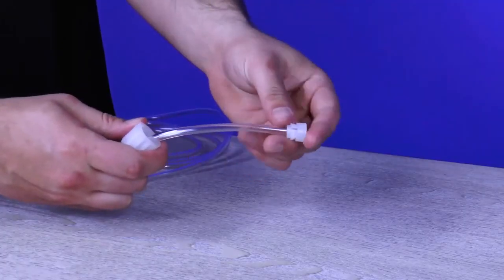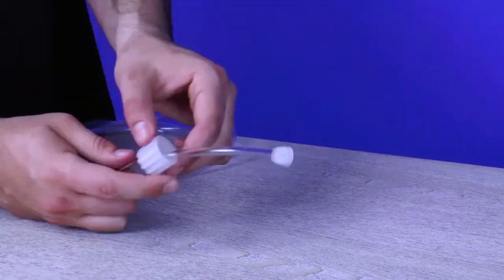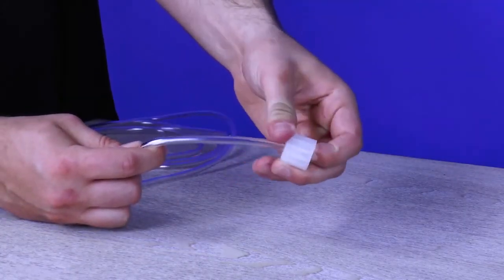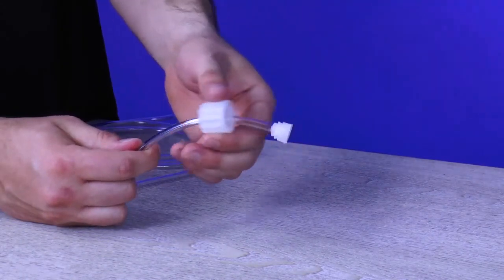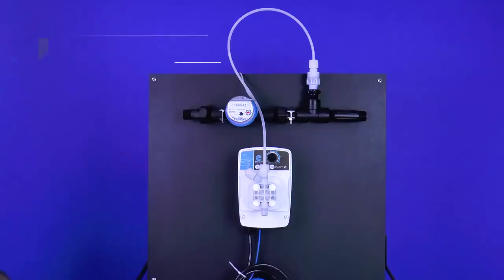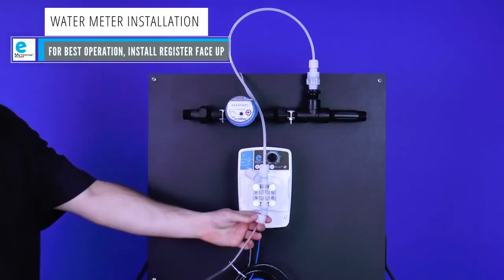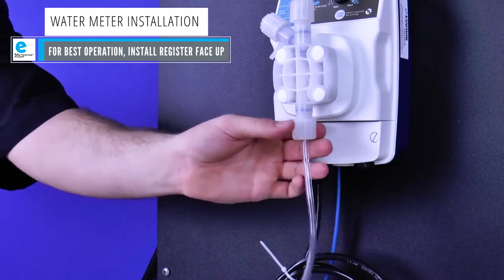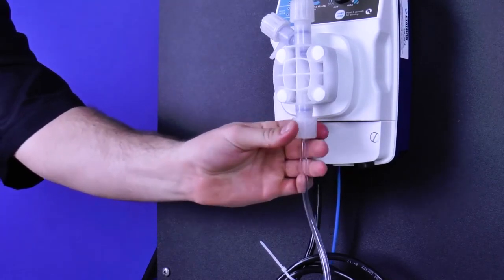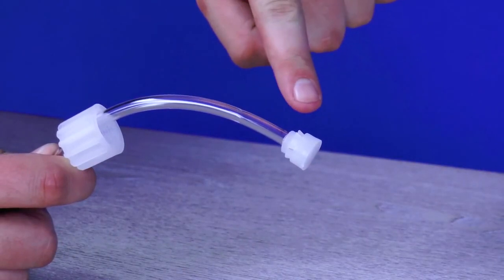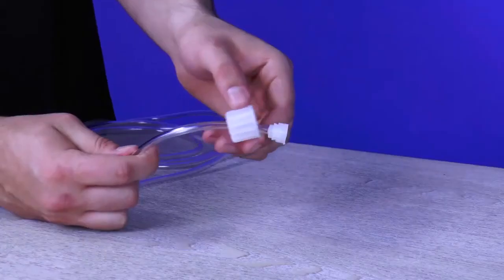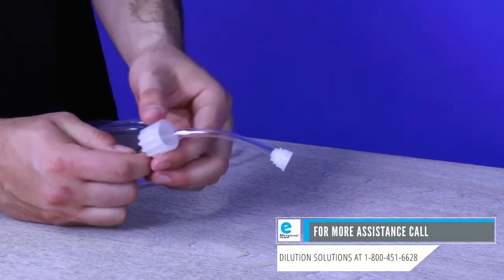Push the collar and nozzle together as close as possible. Pull the tube nut toward the nozzle to compress the collar and nozzle tight together, forming a ferrule connection. Attach the tube and tube connections onto the suction valve by hand tightening the tube nut. Do not cross-thread nor over-tighten. If the tube nut is not securing, recheck the ferrule connection. Pull the tube nut toward the nozzle once more to compress the collar and nozzle together. Retighten the tube nut until secure.